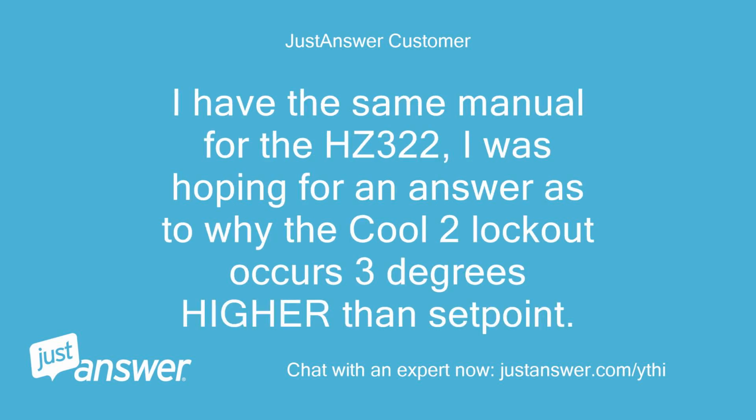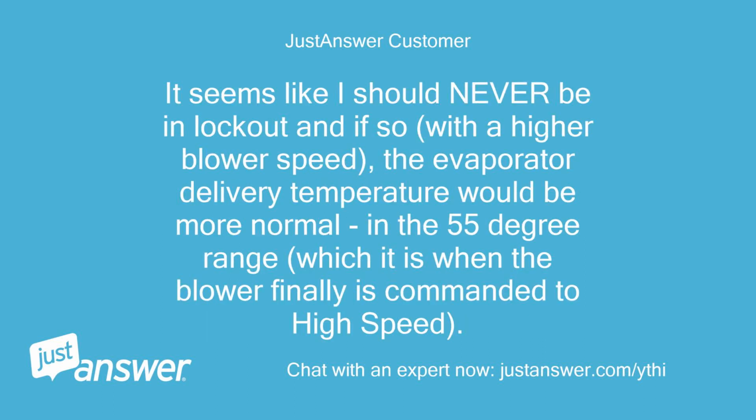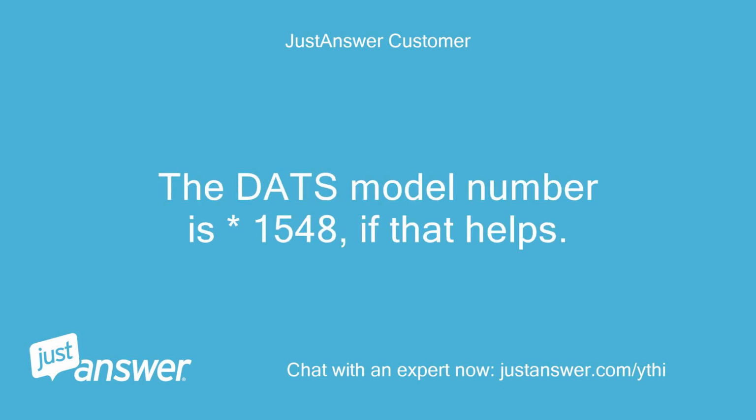I have the same manual for the HZ322. I was hoping for an answer as to why the cool 2 lockout occurs 3 degrees higher than set point. It seems like I should never be in lockout, and if so, with a higher blower speed, the evaporator delivery temperature would be more normal, in the 55-degree range, which it is when the blower finally is commanded to high speed. The DATS model number is 1548, if that helps.